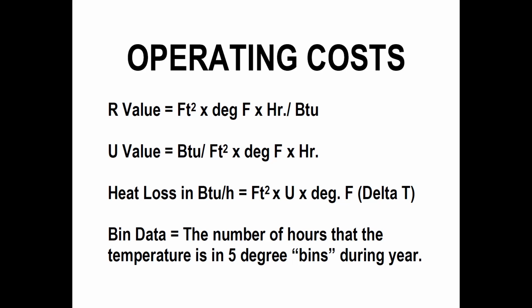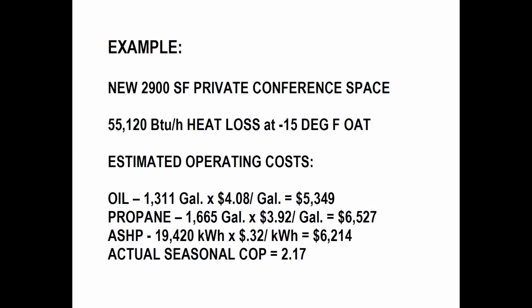So we'll talk about the bin data now. They define a bin as the amount of hours in a year in Concord, New Hampshire for us that the temperature is minus 15 to minus 10, minus 10 to minus 5, minus 5 to 0, and on and on. So over that period of a year, you've got all those hours, and you've got an efficiency for an air source heat pump associated with those different temperature bins. So we use that when we do calculations for what we can assume your usage will be in a year, how many hours it's going to be in those temperature ranges, and how efficient your particular heat pump is going to be at that point. And I think I have an example of it.